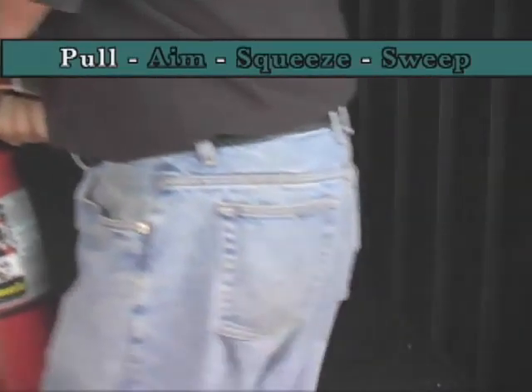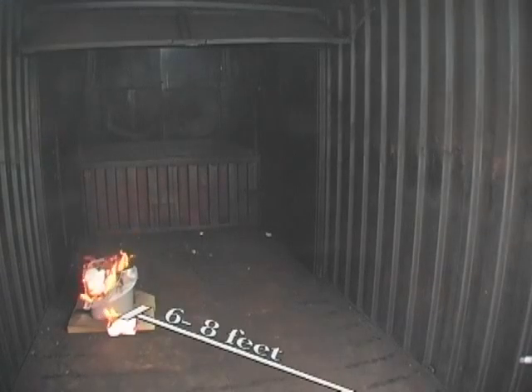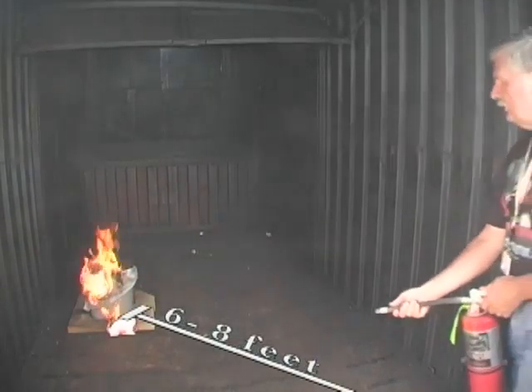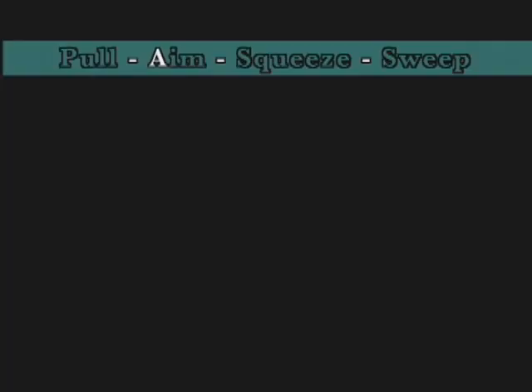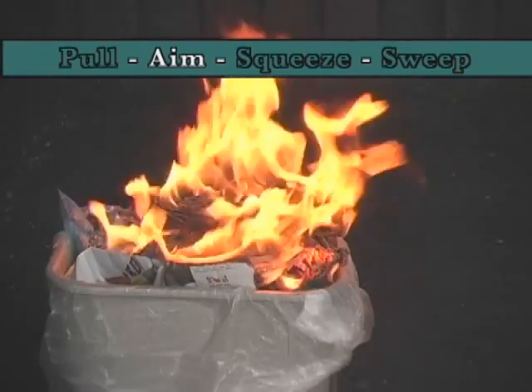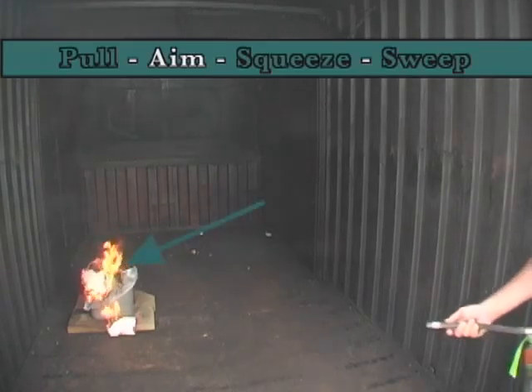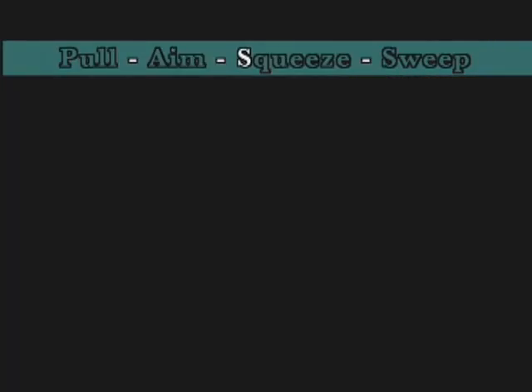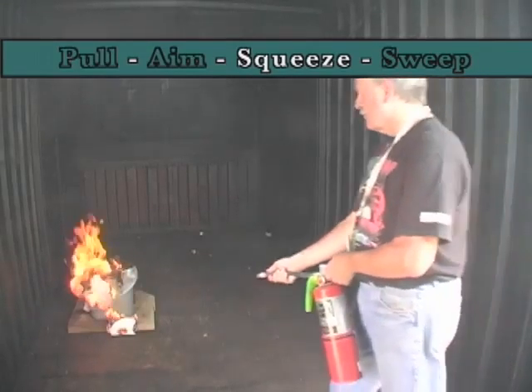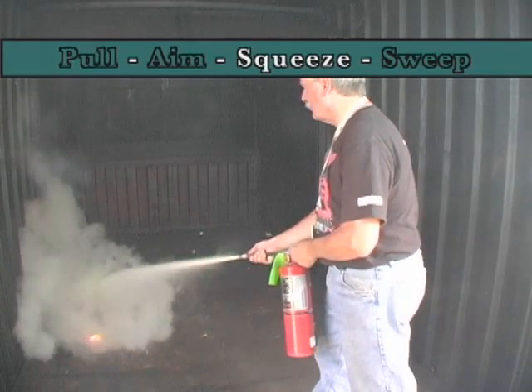Approach the fire cautiously, remembering that your safety is paramount. You should stand 6 to 8 feet from the fire. A stands for aim. Aim the nozzle at the base of the fire, between the fuel source and the flame. S is squeeze. Squeeze the handle to discharge the fire-suppressing agent onto the base of the fire.